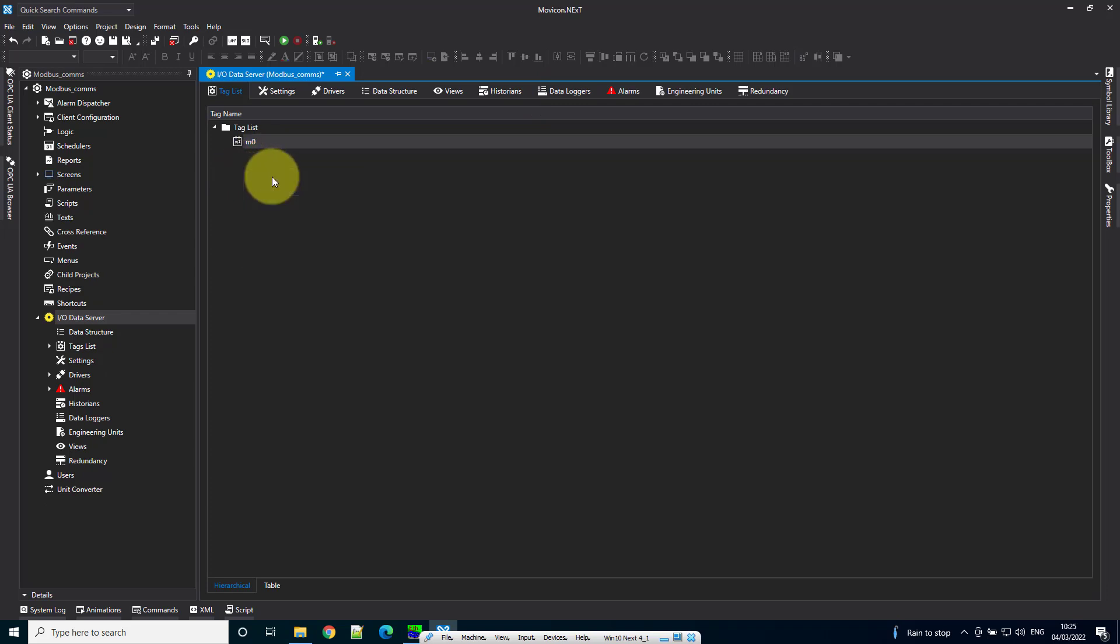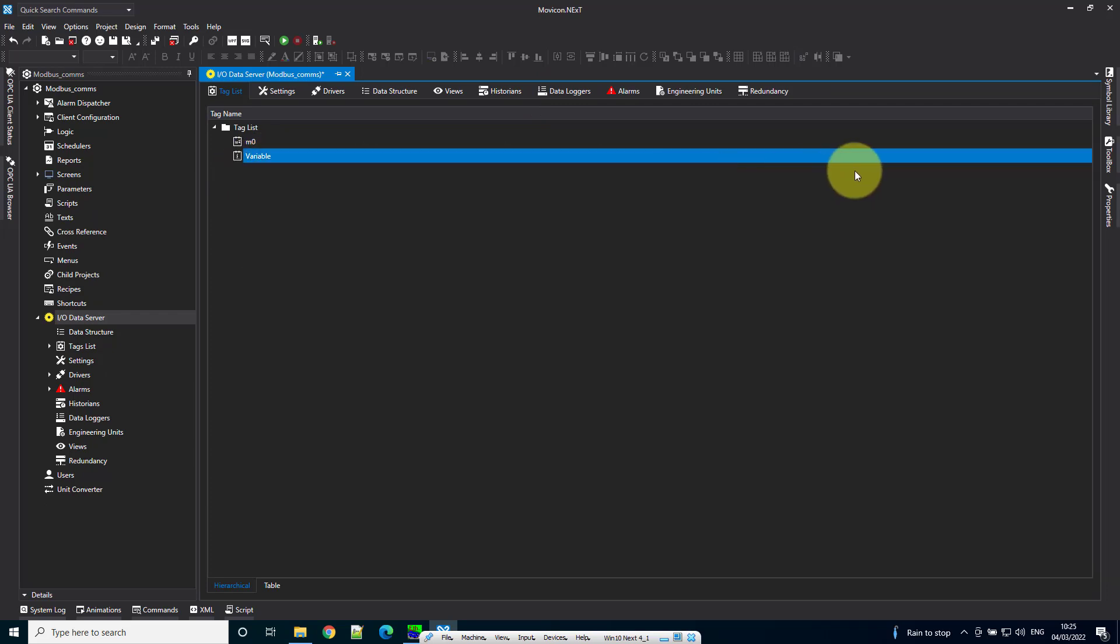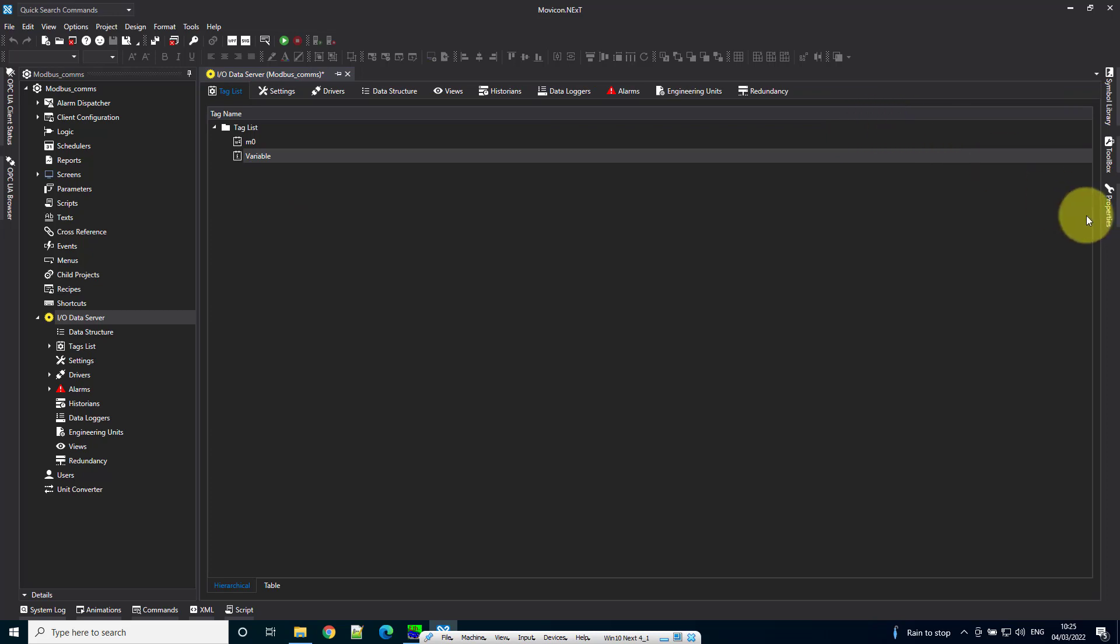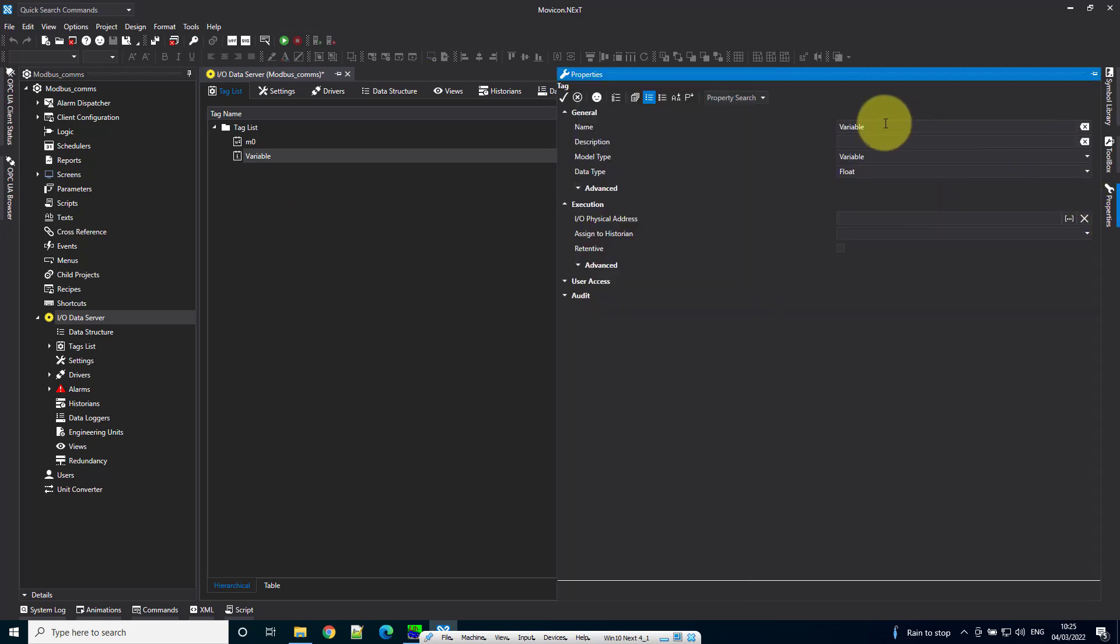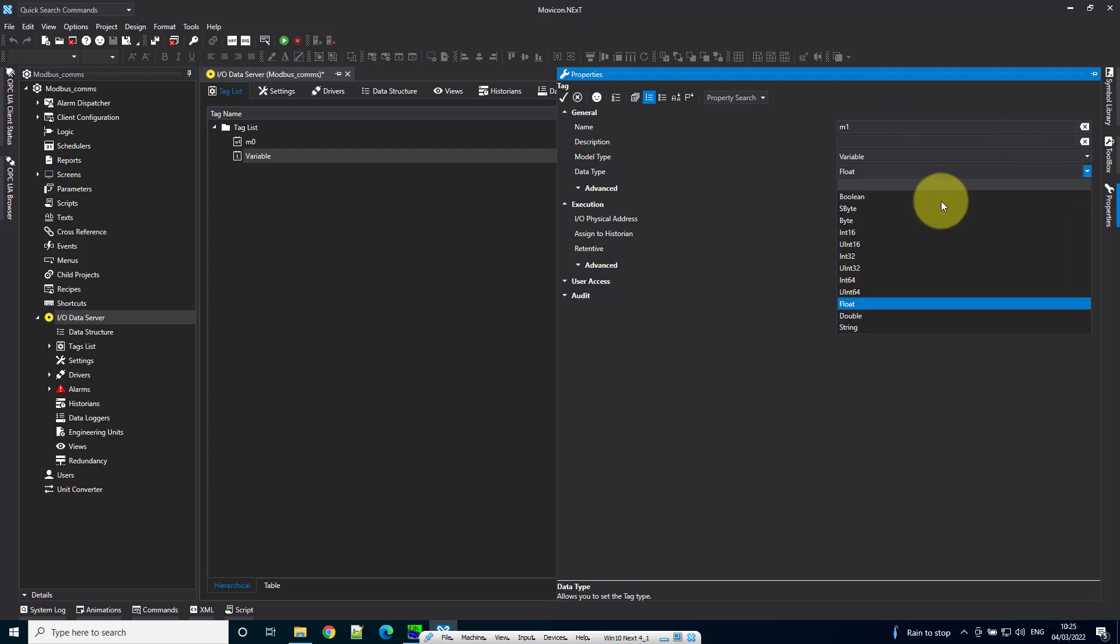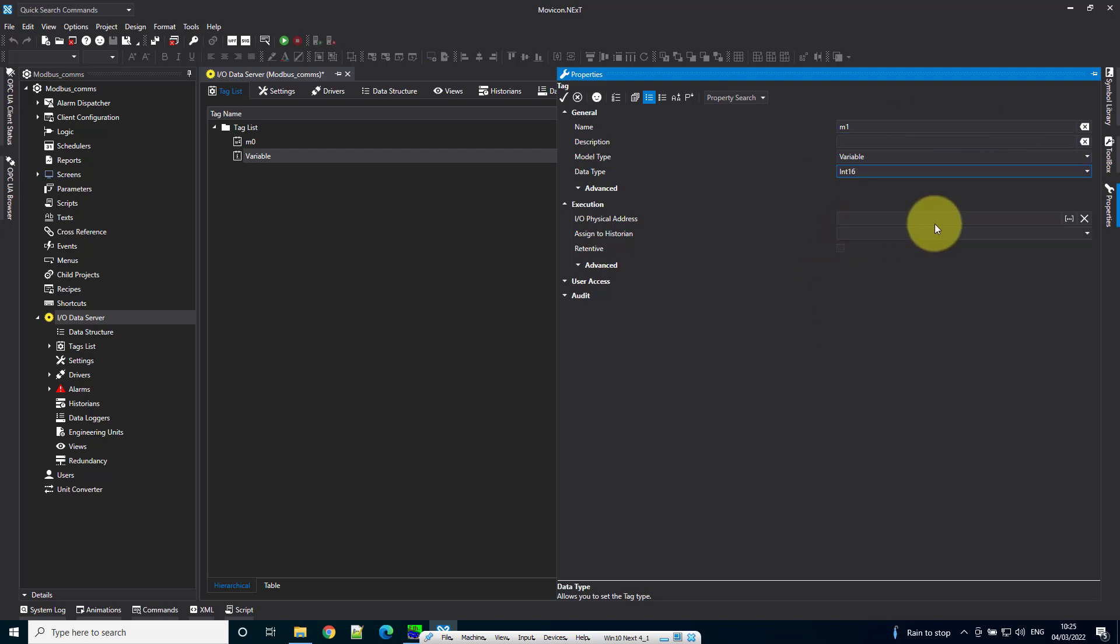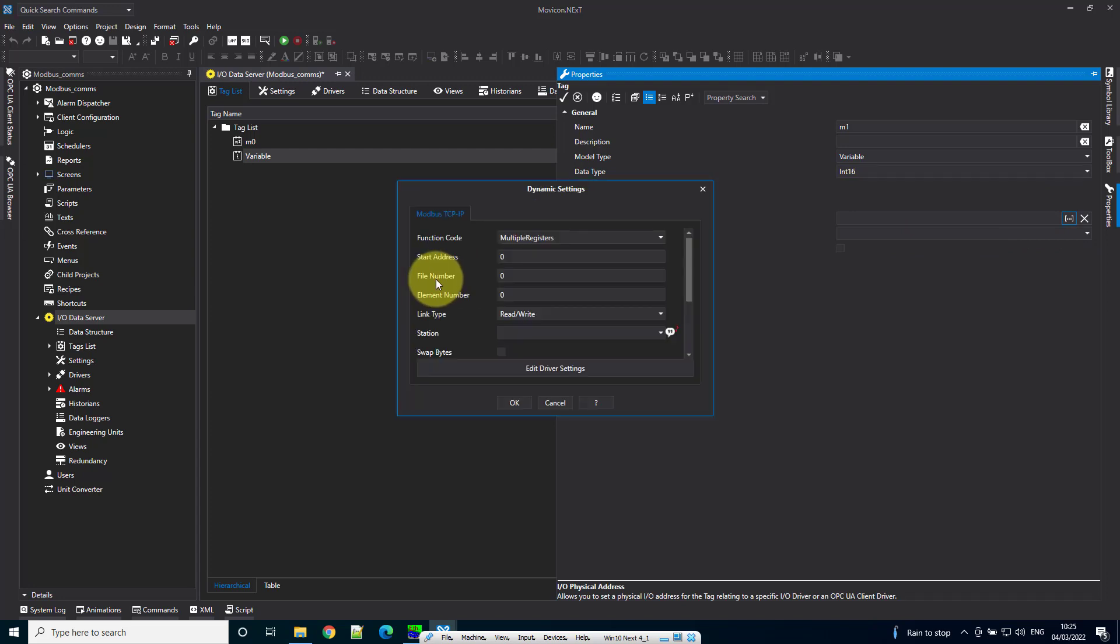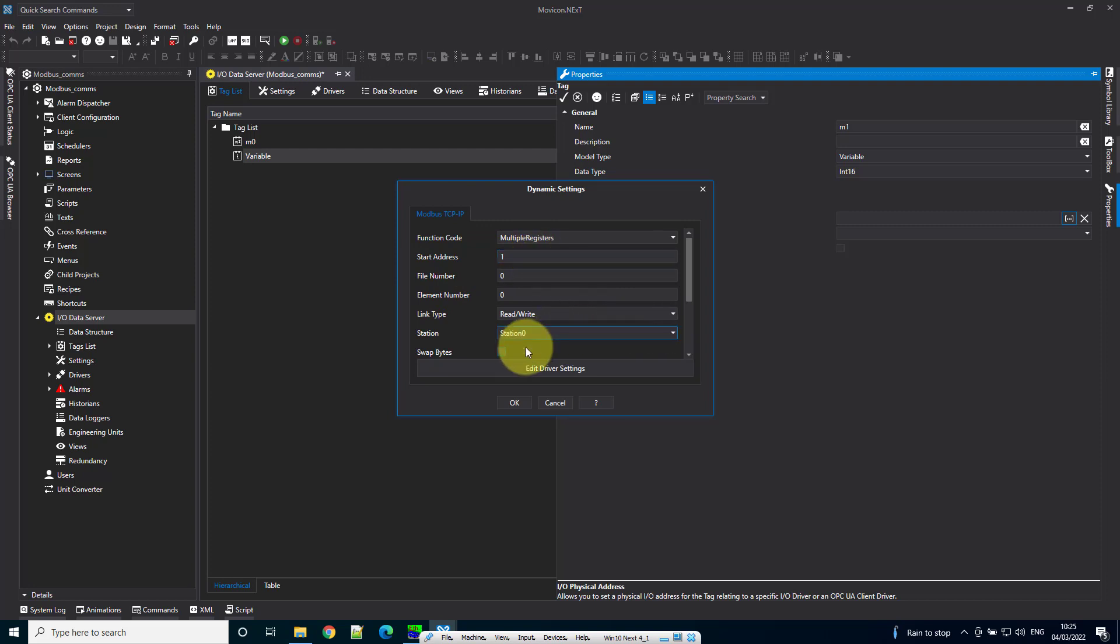Now create another tag called M1. Bear in mind, these tags can be called anything you need. Again, set the IO physical address, but this time the start address should be 1, and the station should be station 0.